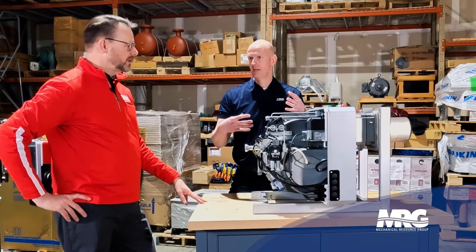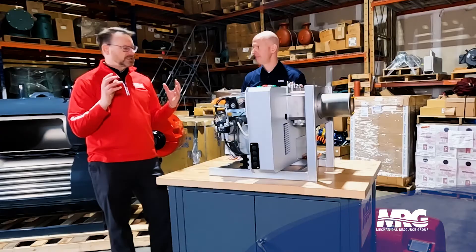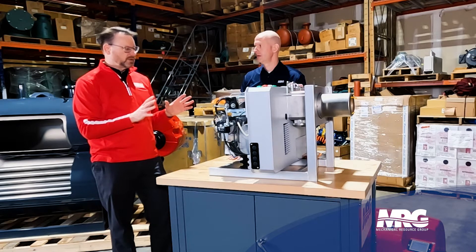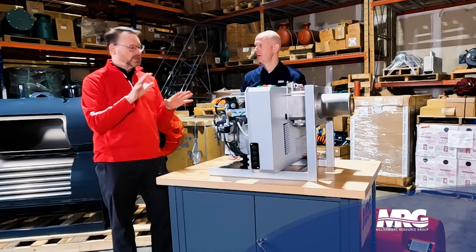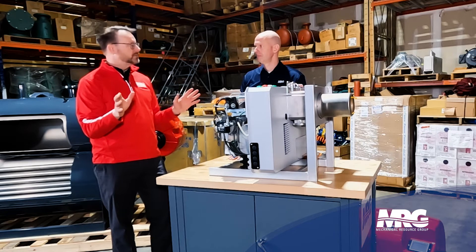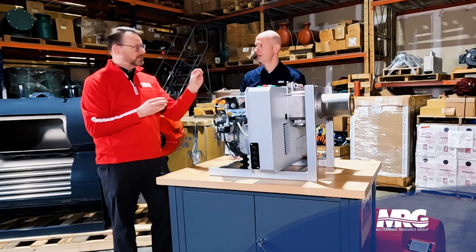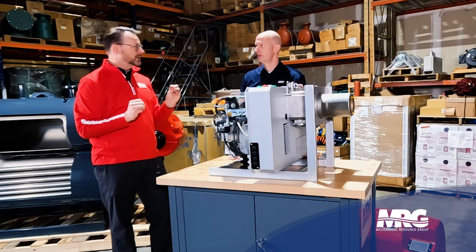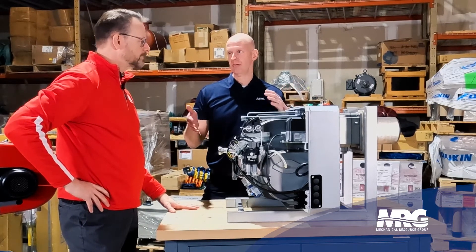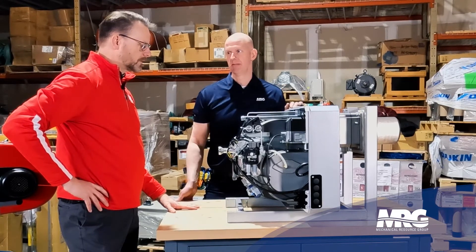It also allows you to synchronize fuel and air over multiple fuels. This unit is set up and provided for dual fuel. Those settings will be unique for oil-to-air, and then we'll have unique settings for gas-to-air — never do the two have to mix or cross over as they would with a single point of motion trying to make those three points play together. That's pretty powerful for critical applications — hospitals, industrial — where you can't be down and have to have a dual fuel solution. You guys have created a solution that takes that into account.